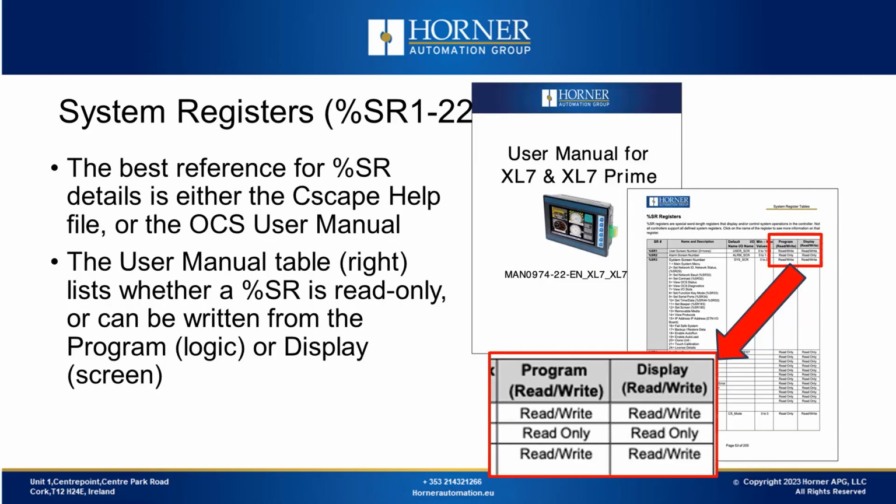Now, the vast majority of system registers are of the word type, ranging from %SR1 to %SR222. We'll focus on these for our discussion today. Unlike S bits, which are read-only, SR registers can be a mix of read-only and read-write.